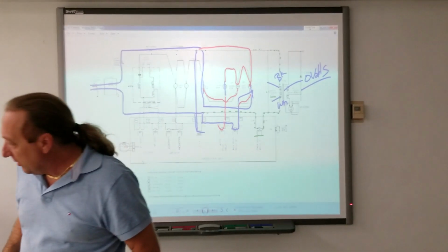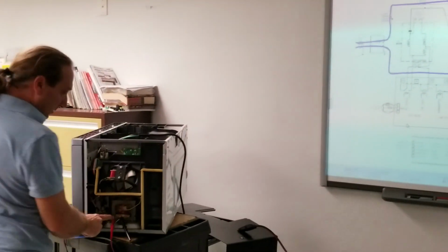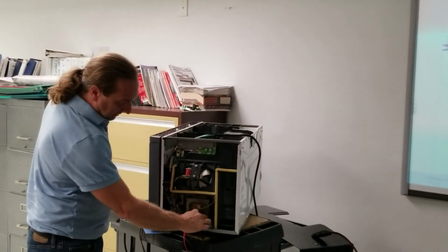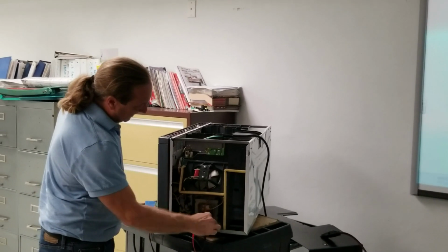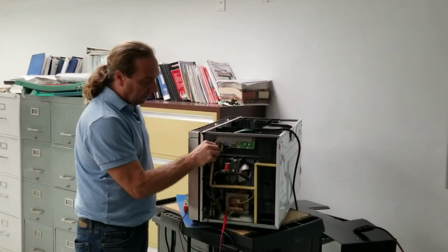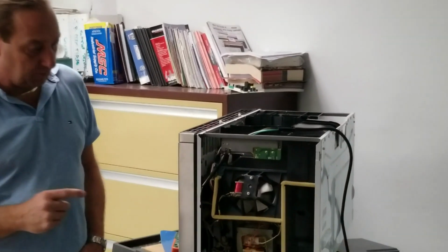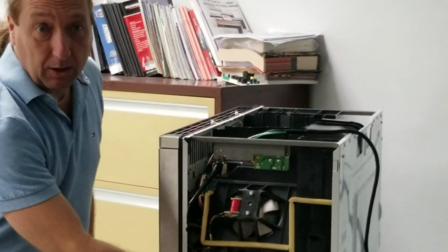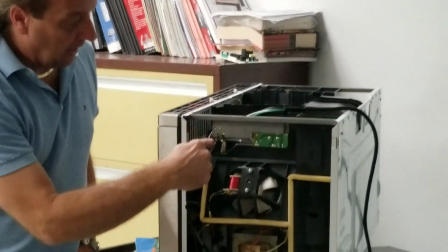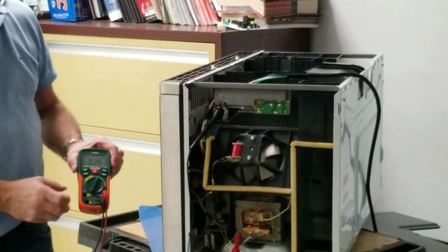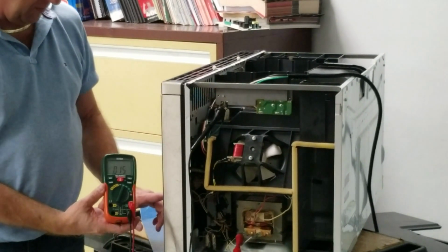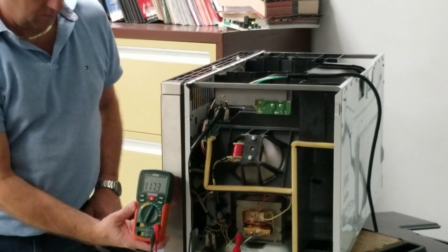So I'm going to leave my meter lead on the black wire on the transformer. And I'm going to take this white one off, and it just so happens I have a ground wire right here on the frame of the machine. So I'm checking black, which is power coming into the transformer. I'm checking ground. And I'm going to press start. There you go. I have 120.